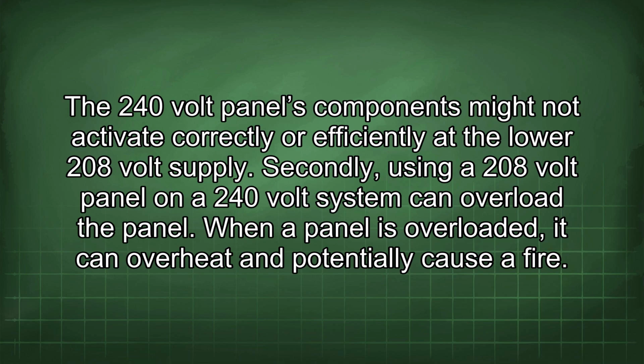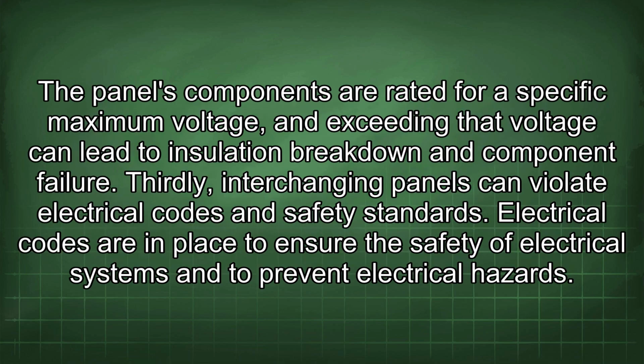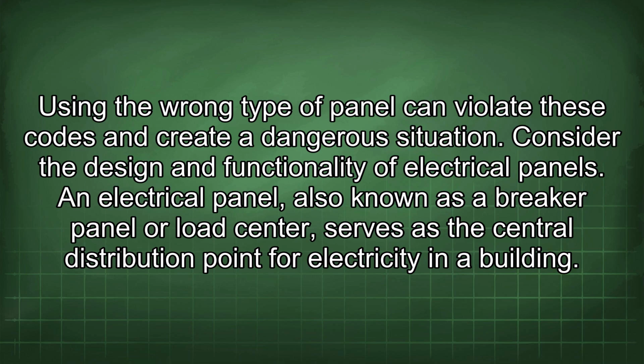Secondly, using a 208-volt panel on a 240-volt system can overload the panel. When a panel is overloaded, it can overheat and potentially cause a fire. The panel's components are rated for a specific maximum voltage, and exceeding that voltage can lead to insulation breakdown and component failure. Thirdly, interchanging panels can violate electrical codes and safety standards. Electrical codes are in place to ensure the safety of electrical systems and to prevent electrical hazards. Using the wrong type of panel can violate these codes and create a dangerous situation.